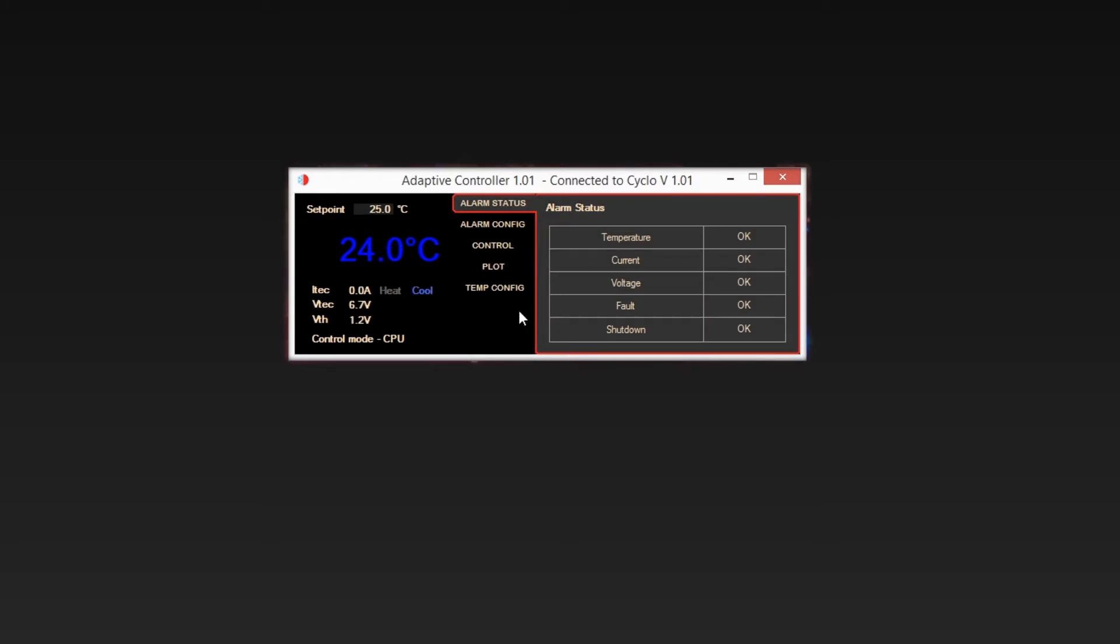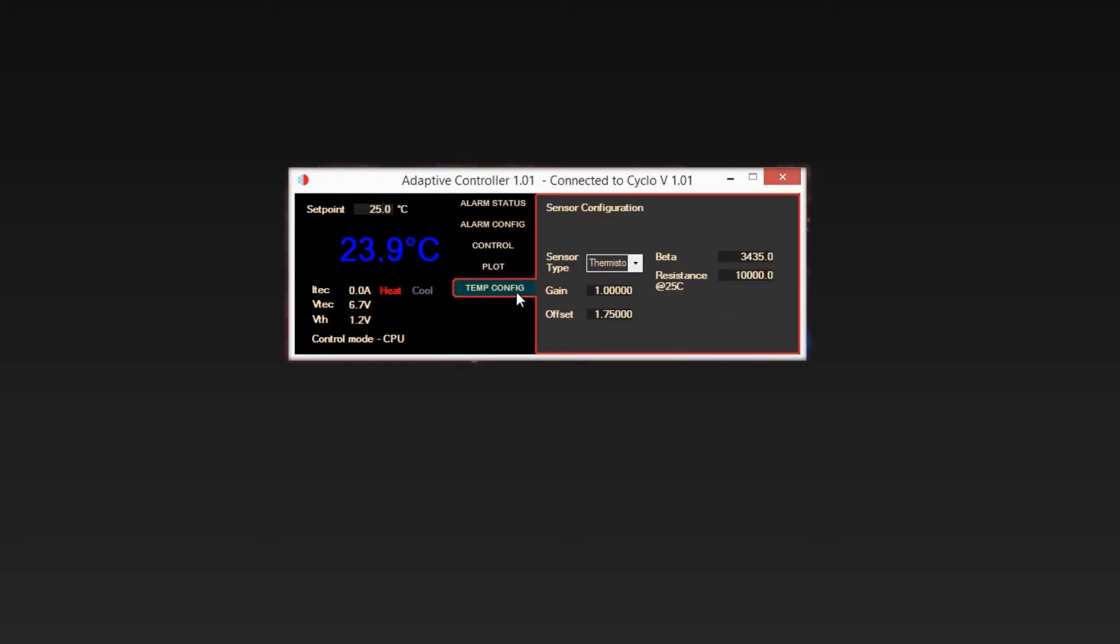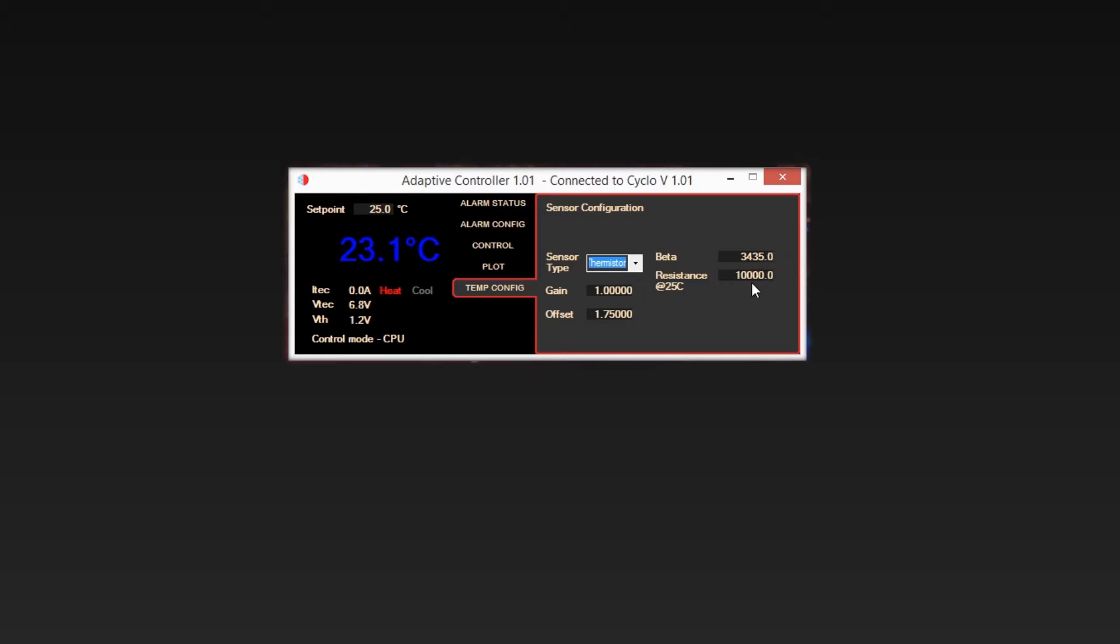Firstly, go to the Temp Config tab. This is for sensor configuration. In this dialog box are the settings for the thermistor used. Refer to individual data sheets for specific thermistors. The Cyclo is pre-calibrated for an NTC 10K sensor. See Cyclo user guide for details. If using a different thermistor, these calibration values will need to be entered.